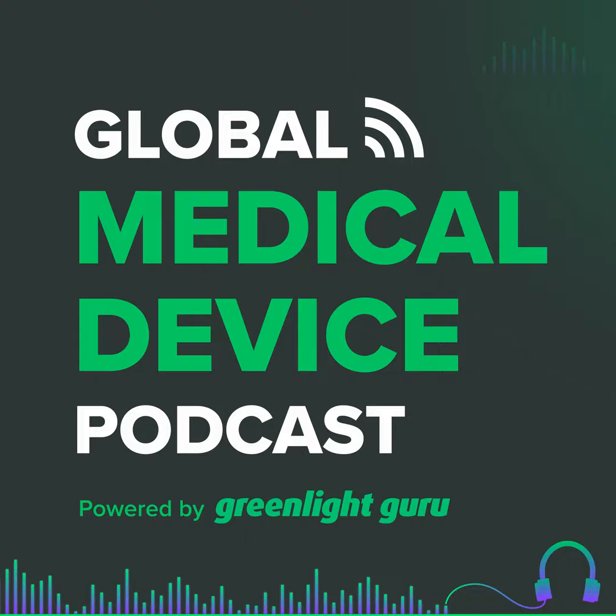But if you are going to need clinical data, even if it's a non-significant risk device, as we talked about before, I think you're wise to vet that with the FDA in a pre-sub in advance first, even though you're not required to. Some companies take the attitude, well, we don't want to create a problem where none exists. And so they'll say, well, we're not going to tell FDA about that. Well, I say, okay, fine, that's your decision. You don't have to. But here's the risk that you're taking.